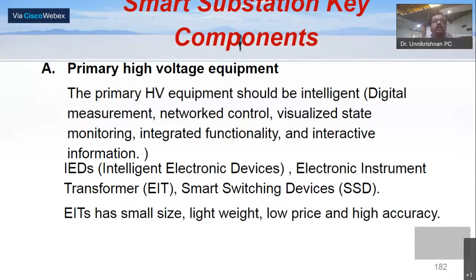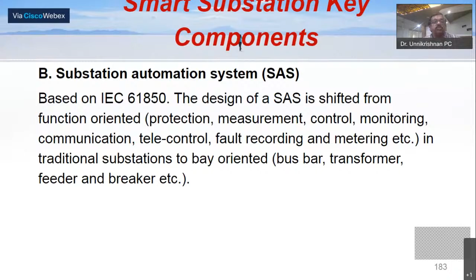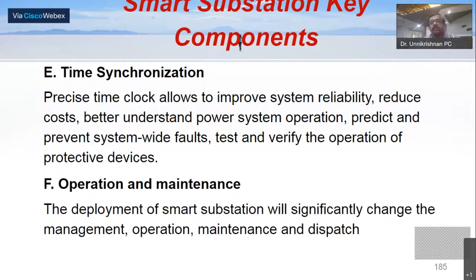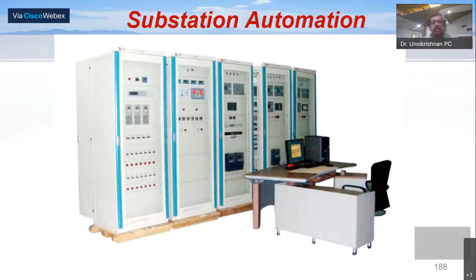The different components of a smart substation: one is the primary high voltage equipment, IEDs. Then the substation automation system, SAS, based on IEC 61850. Then protection devices, metering devices, time synchronization, and operation and maintenance, so almost all operations will be automated. Then auxiliary systems such as video monitoring, fire alarms, etc. Substation automation is a very important part.